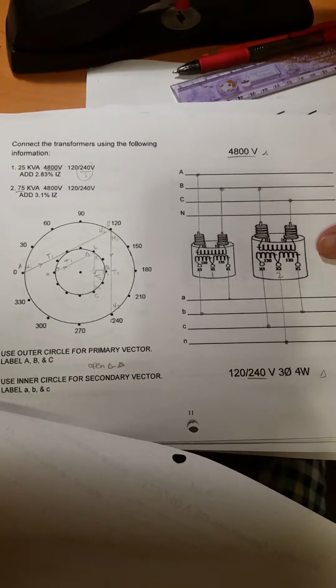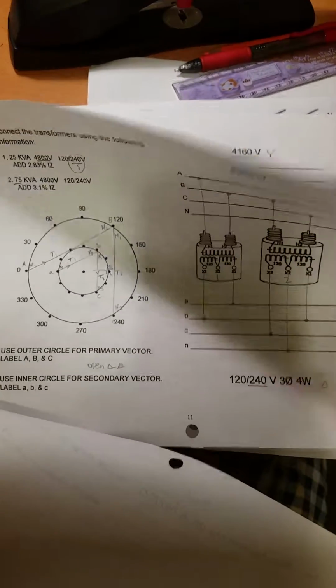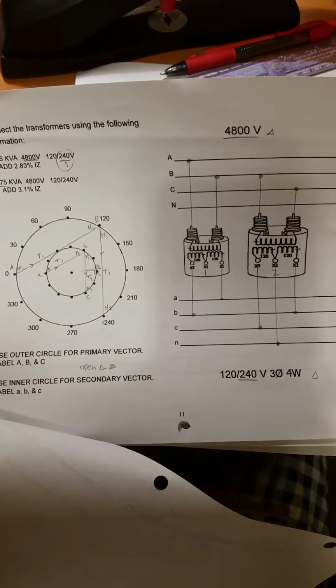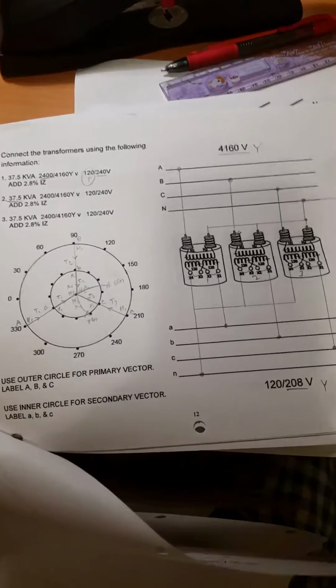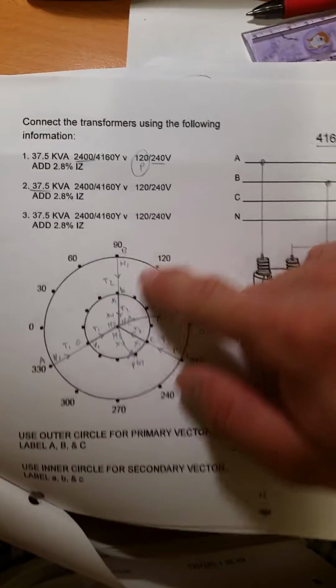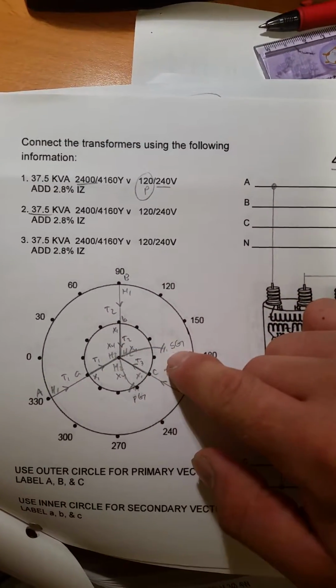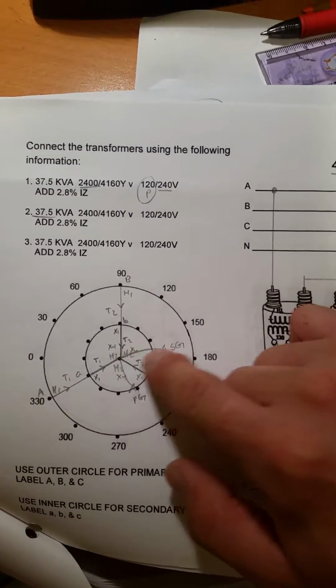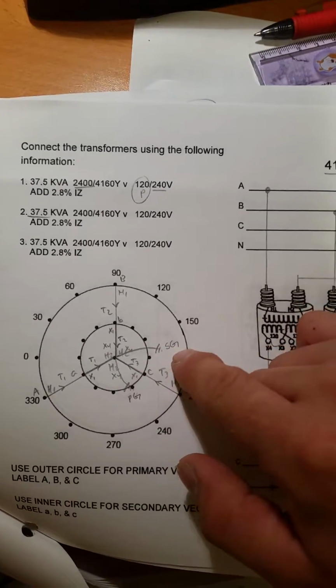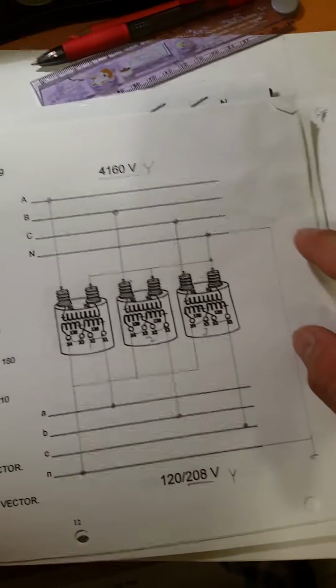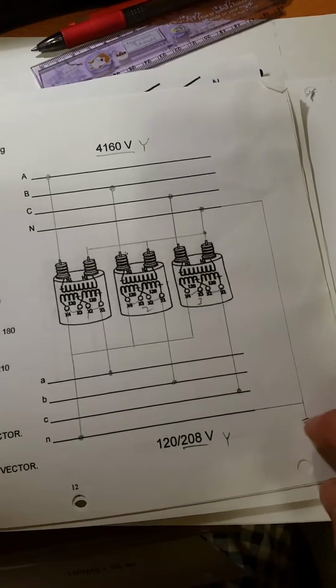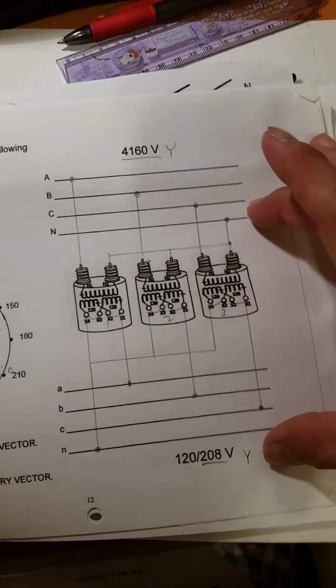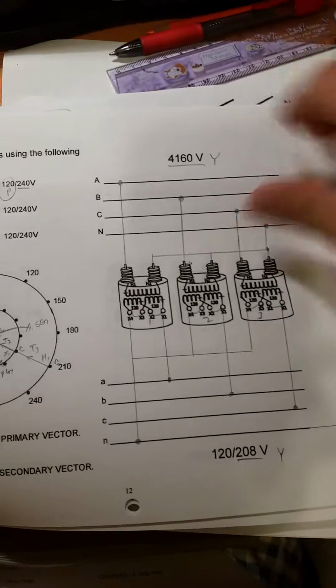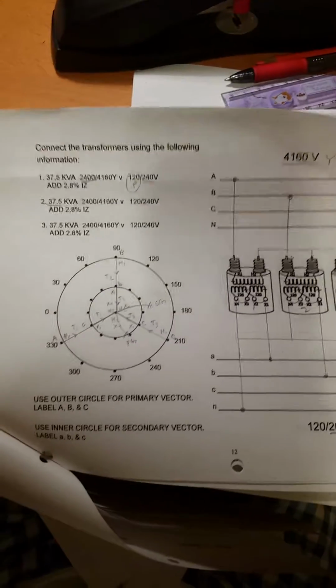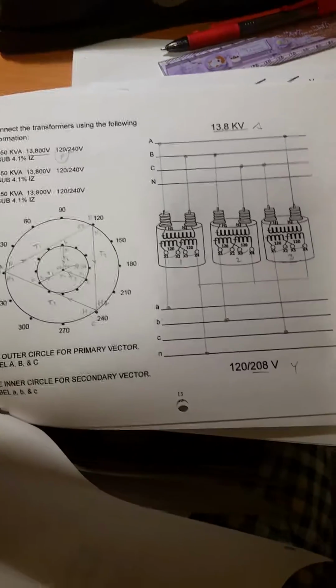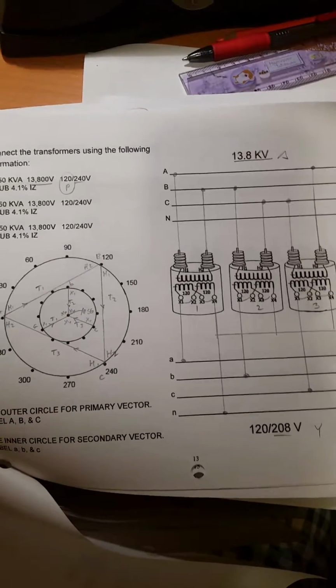Another open bank here - Y to Y. Y to Y, you always tie the ground together. At the same spot in the middle, I drew a ground rod, and I put secondary ground, primary ground, and right here I drew a line and grounded the primary neutral and the secondary neutral together. Y always tie - study up on that, memorize that, whatever. That's how I did this one.